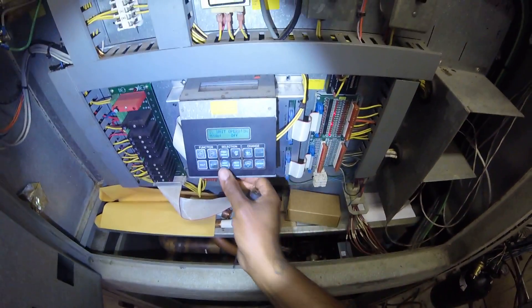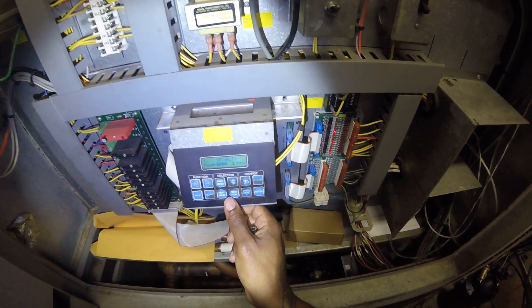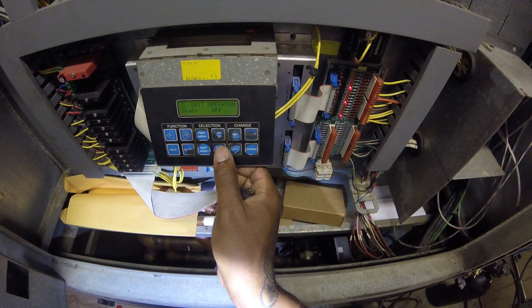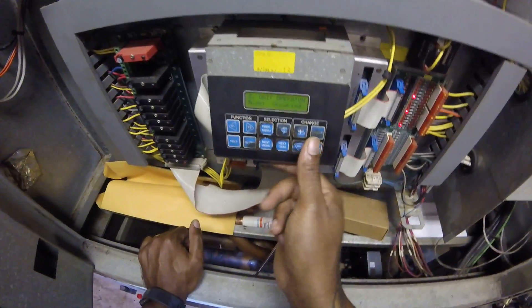So I got one circuit running. I'm going to keep getting up some air because it's a kitchen area — 77 degrees up in there now. I found my leaks, so they can have one circuit running. I just go here and put it in occupied mode. There's not a time clock — sometimes they got a schedule on them, but this kitchen it runs 24/7 basically.